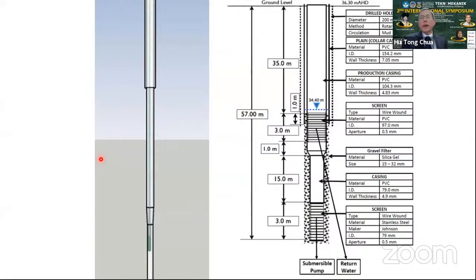This is the heart of the technology of the ground source heat pump. And you can see here to the left is the doublet system, whereby instead of the conventional 2 borehole system for a geothermal low enthalpy air conditioning system, we have here instead just 1 borehole. The submersible pump is located here. Now, because this neighborhood area is located at a fairly elevated site, which is atypical, the water table is pretty low, sorry, I beg your pardon, the water table is 35 meters, and so the borehole has been drilled to a depth of 57 meters.